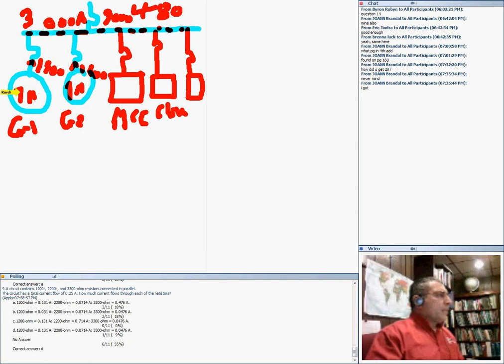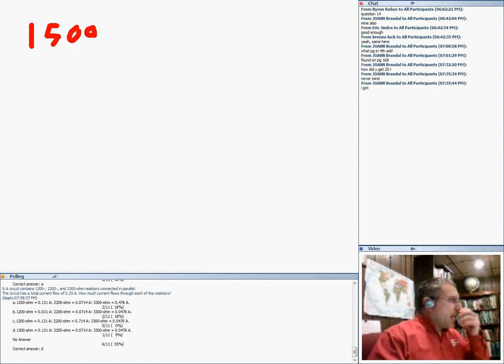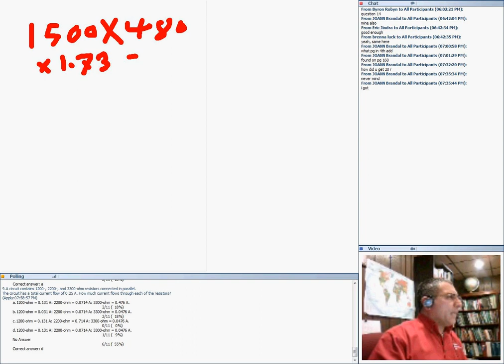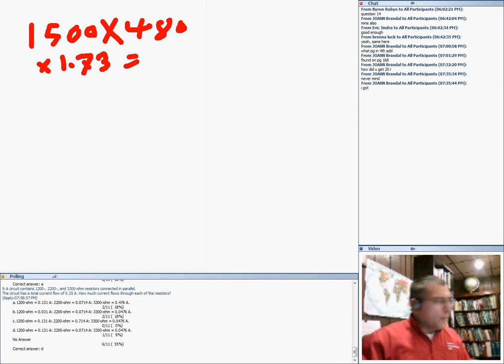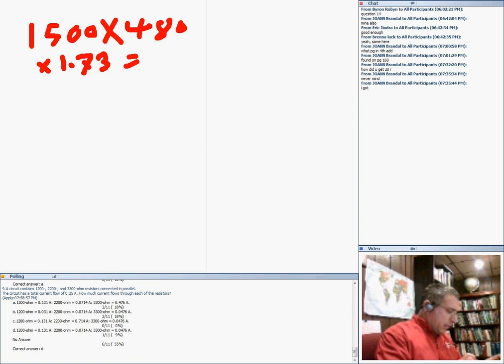Just to give you an idea, guys, when we parallel these 2 generators, if I have 1 generator, it will be only 1500 amps. If you multiply this by 480, and multiply this also by 1.73, that's basically the amount of power that you're going to get. Because it's 3 phase, divide by 1,000 to get the kVA. Don't forget to divide by 1,000. You get the equivalent of 1.2 megavolt amp. Mega, not K.